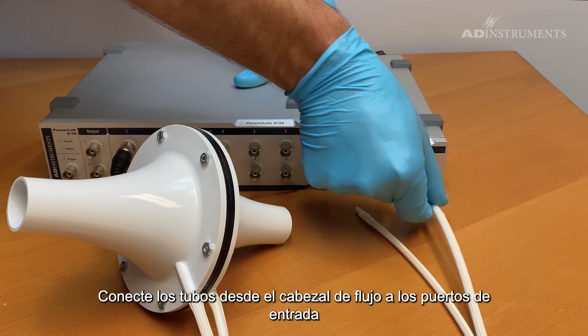Connect the tubes from the flow head to the input ports on the front of the spirometer. Note that you can swap these if you find that the signal is upside down.